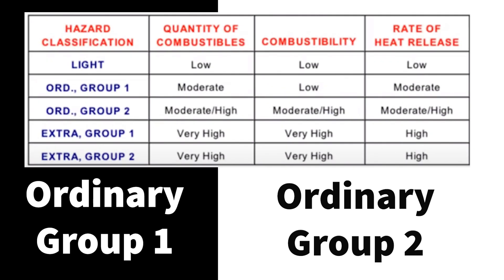Ordinary hazard occupancy breaks into two groups: Group 1 and Group 2. As you can see on our hazard classification chart, ordinary hazard Group 1 is moderate on quantity of combustibles, low on combustibility, and moderate on rate of heat release. When we go to ordinary Group 2, everything across the board goes to moderate-high.